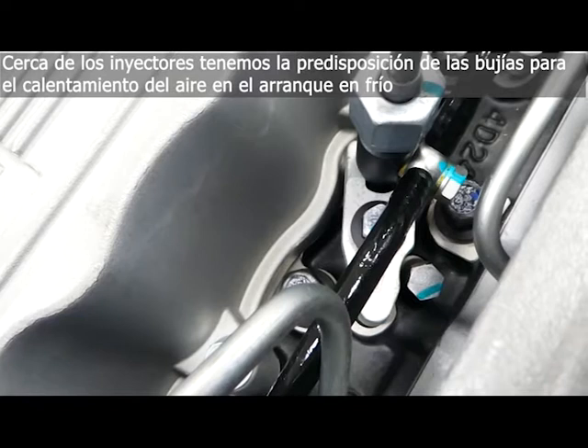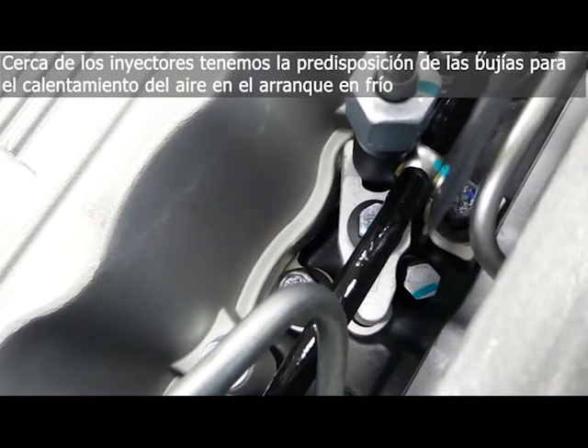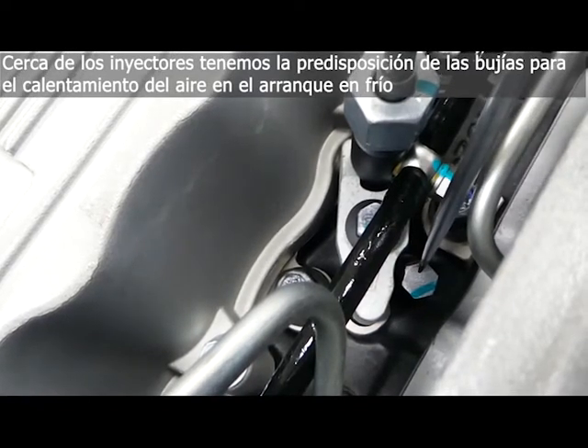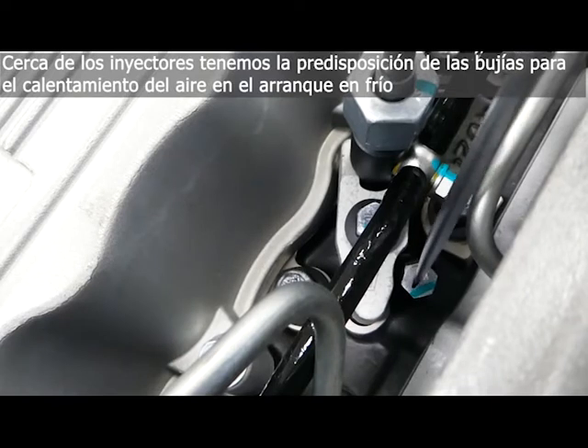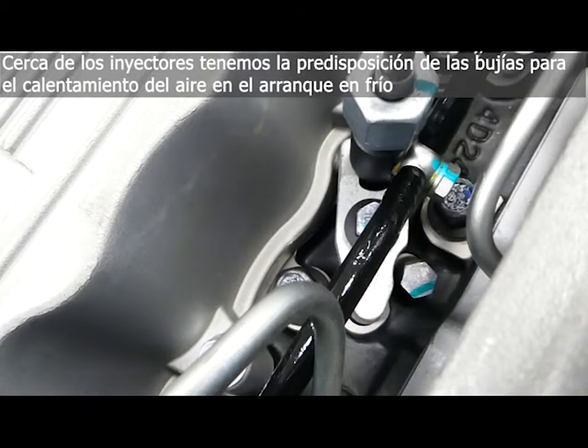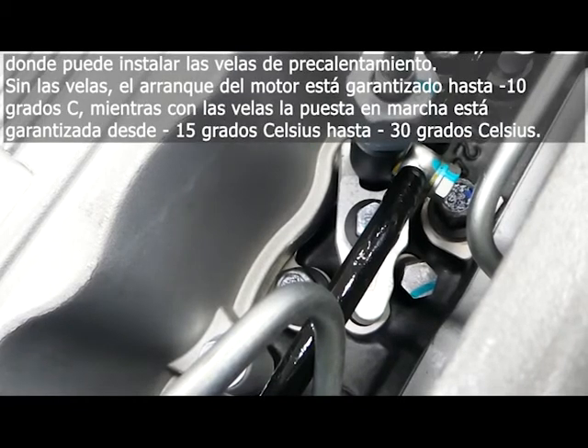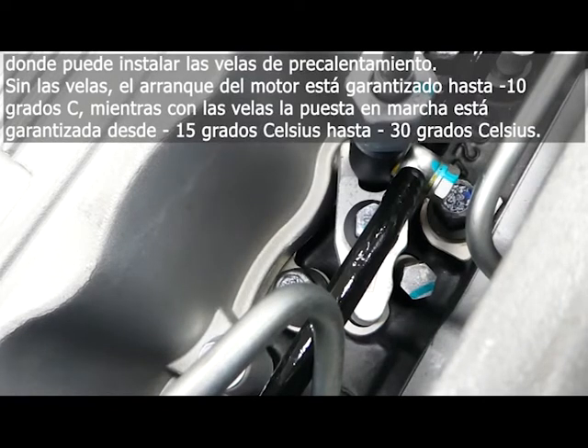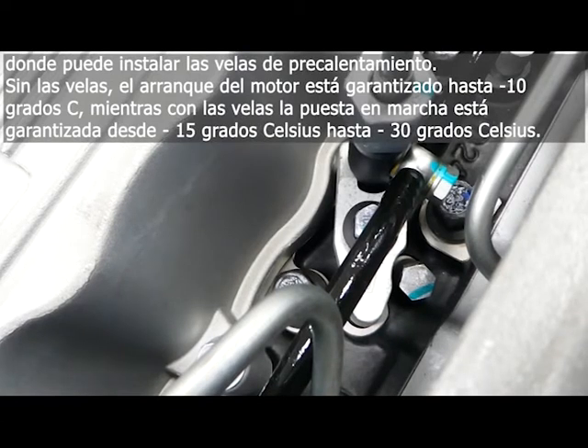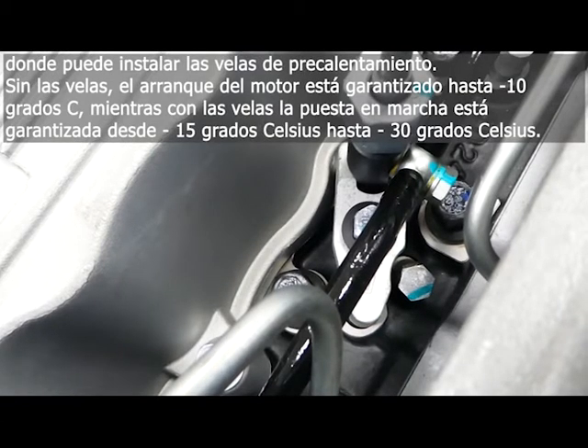On the cylinder head we have already prepared the position in order to install the glow plug heater system. That is mandatory starting from minus 15 degrees Celsius, and this system is able to ensure the cranking and start of the engine down to minus 30 degrees Celsius.